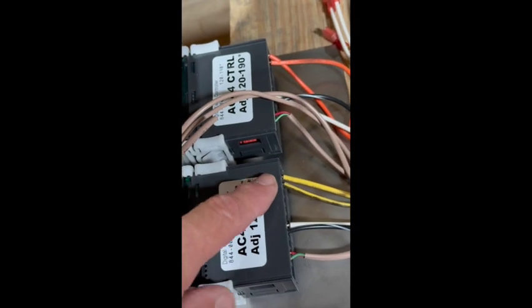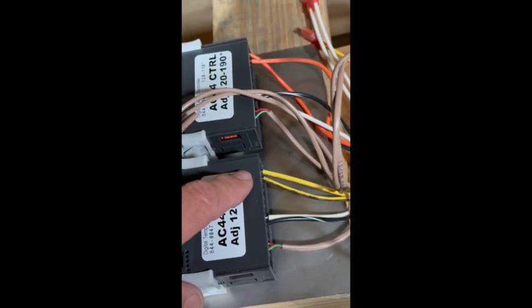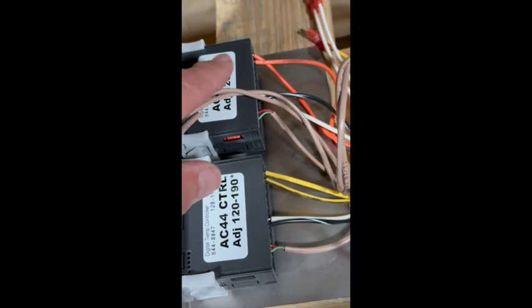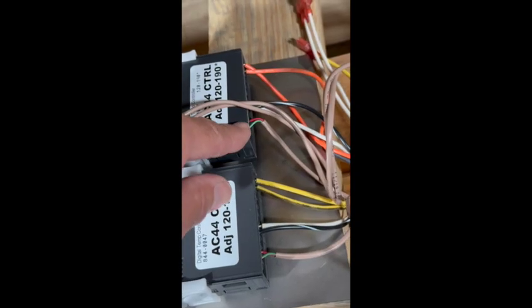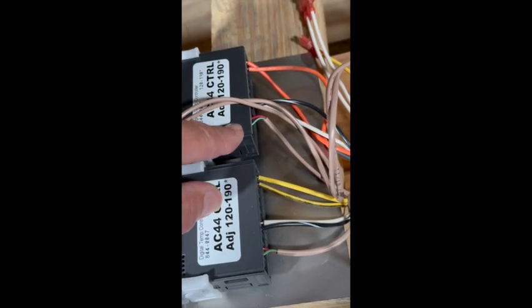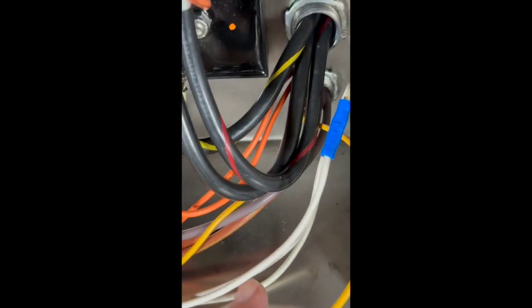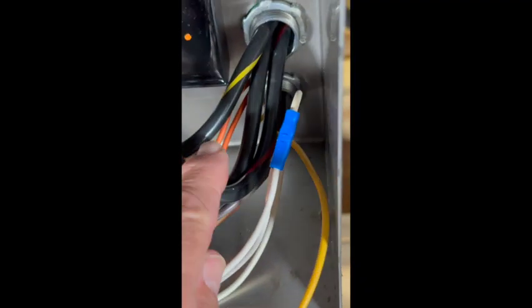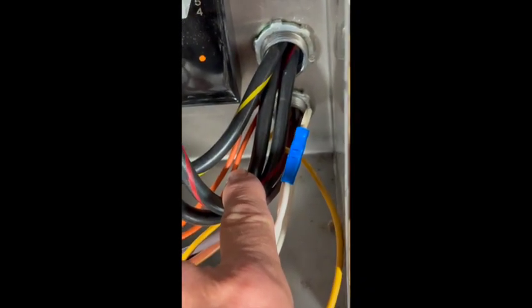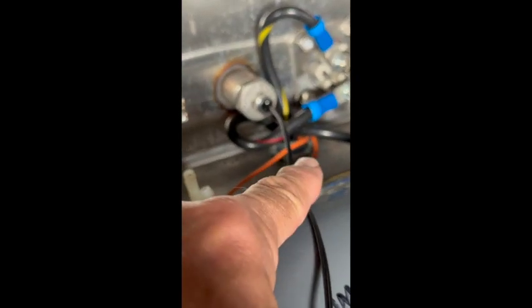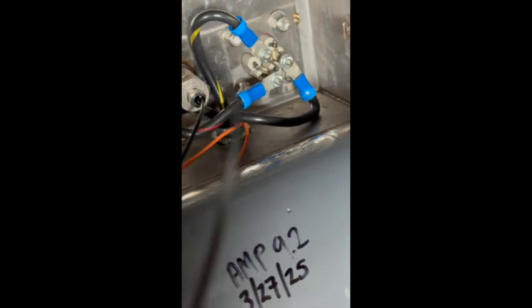Remember, orange is always going to be the wash side and yellow is always going to be the rinse side. So that's how you can know the difference between which wires you need to pull. We're going to be working on the probe wire that's connected to the wash side, and we need to get that probe wire over to the heater control box. So we're going to go through that conduit, come up through the bottom of the box, and eventually the probe wires are going to connect to this thermistor.